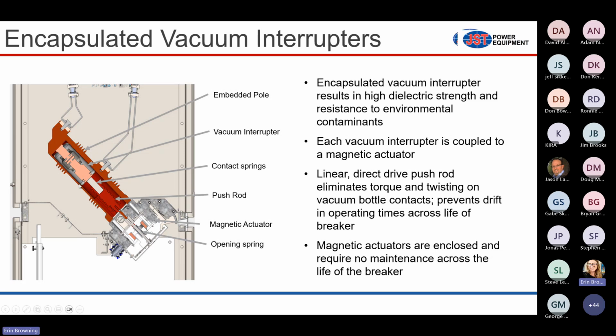So again, this is the vacuum bottle. There are contacts inside of here. These contacts open and close when you have a contingency event, a short circuit event. You're going to have a high amount of current flowing through this vacuum bottle. The protection relays that the customers are using are going to recognize that fault event and issue a trip command to the circuit breaker. That trip command goes to the controller in the low voltage cabinet. Once that controller receives the trip command, this magnetic actuator moves in the downward position very quickly, and these vacuum bottle contacts open.